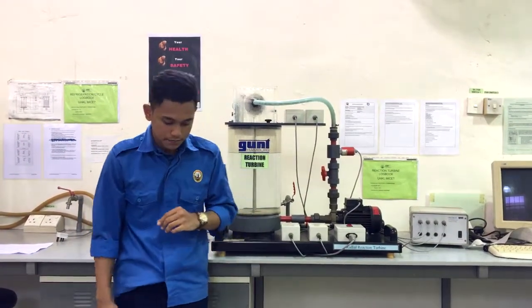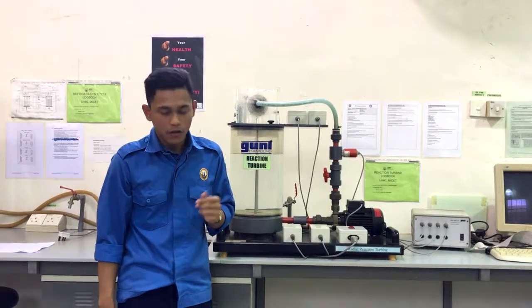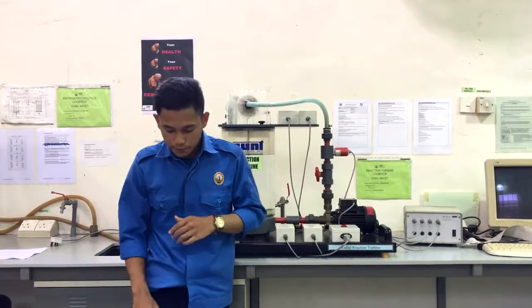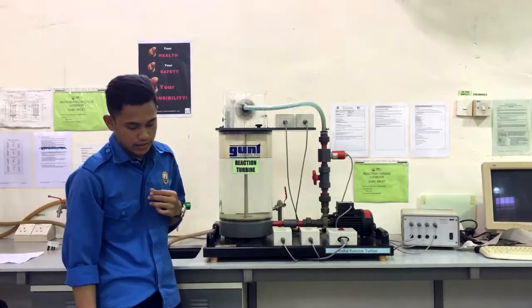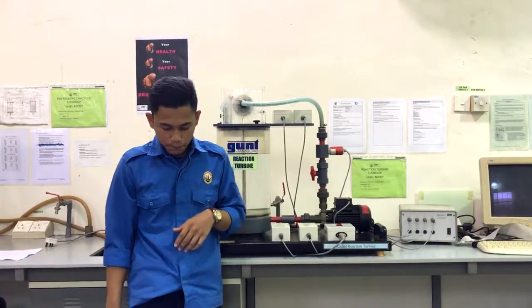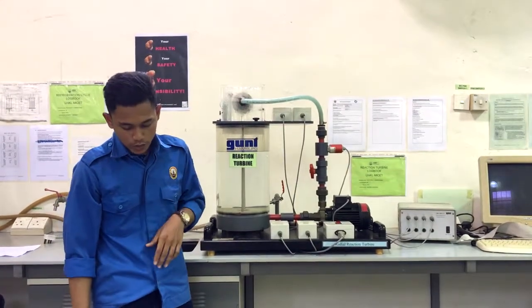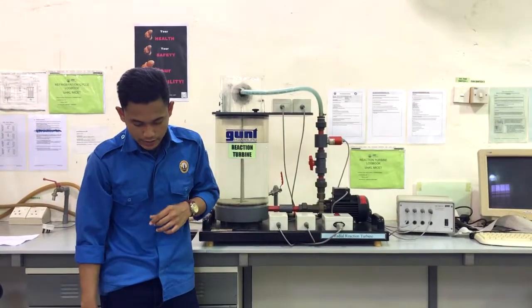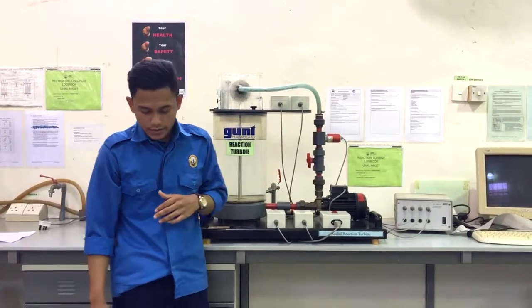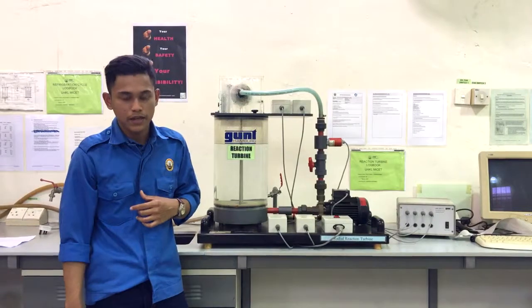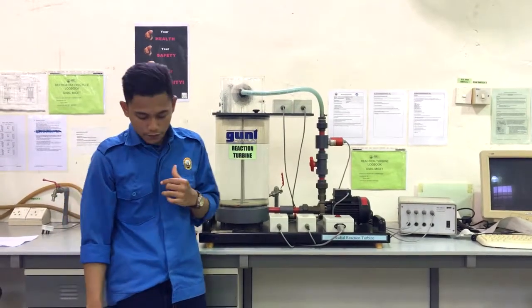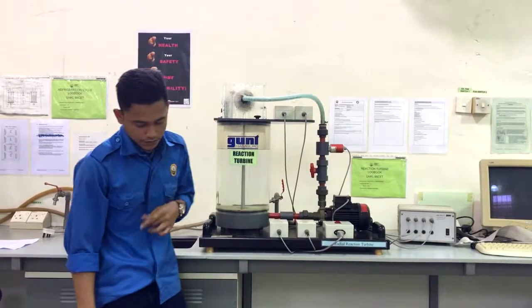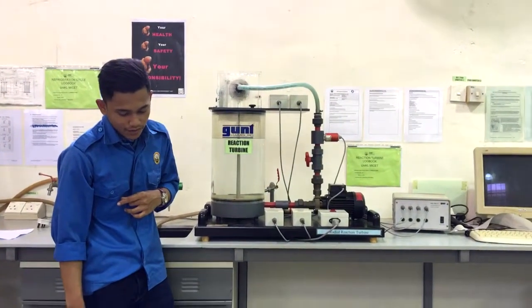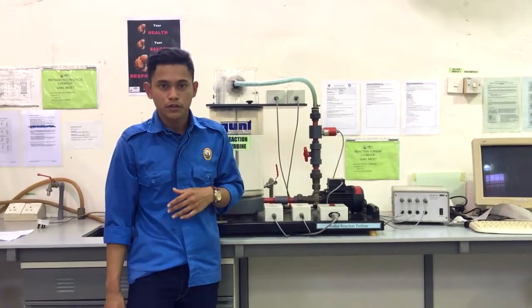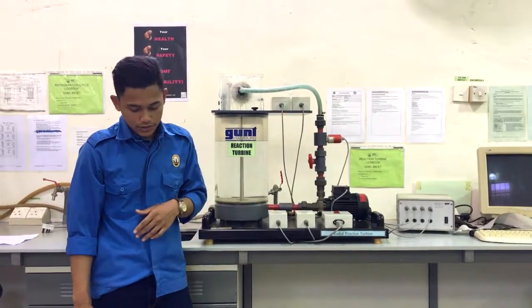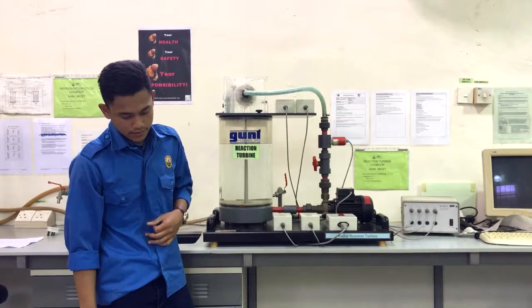Next, for the guide mechanism. The guide mechanism is the arrangement of blades and vanes which will guide the water towards the runner, and allow the water to enter the runner without shock. The guide vanes turn the relative velocity at the inlet of the runner tangential to the vane angle, and thus the result is entering of the water without shock. Then it allows the water to flow without forming eddies.